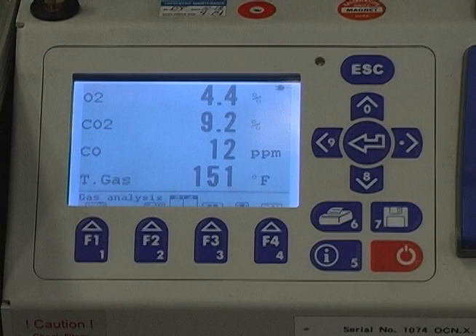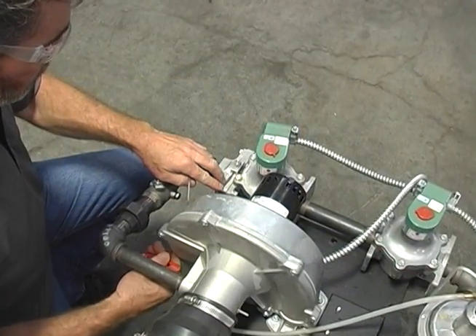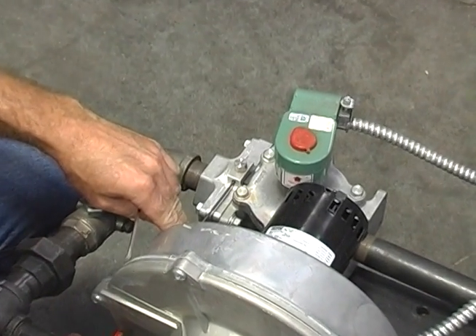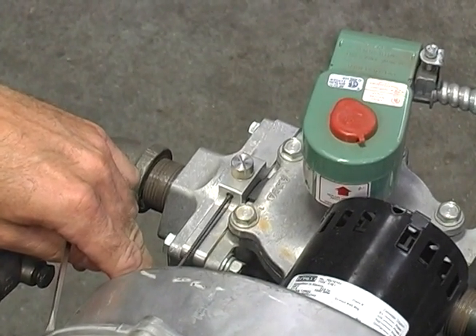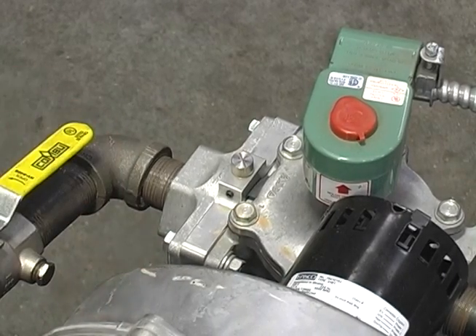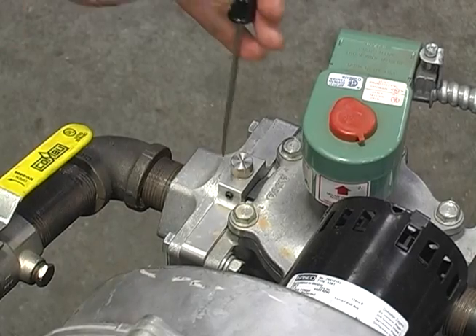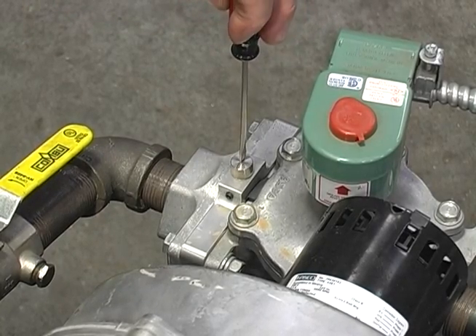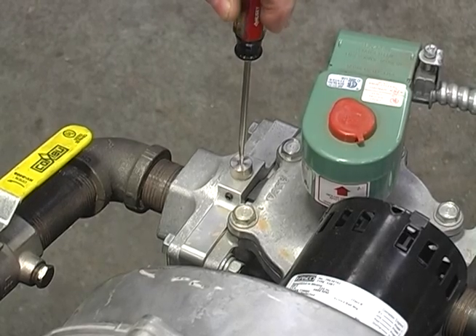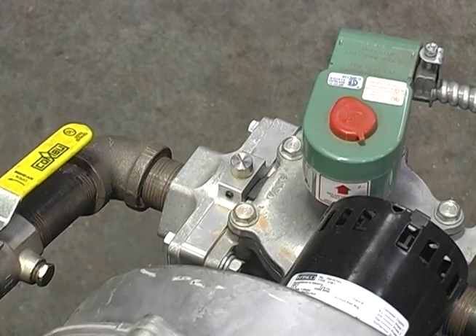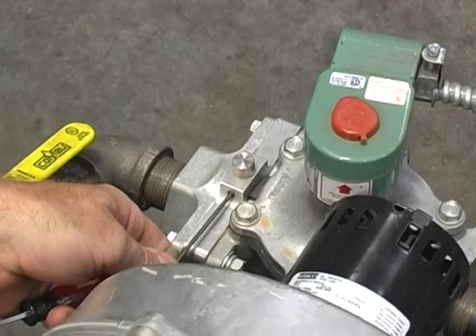At high fire, carbon dioxide level must be between 8.5% and 9.5% for natural gas and between 9.5% and 10.5% for LP gas. If the level is in this range, no adjustment is required or recommended. If the CO2 level must be adjusted, the high fire CO2 adjustment is made on the gas valve. First, loosen the set screw on the side of the valve body. Adjust the valve orifice clockwise to reduce gas flow and counterclockwise to increase gas flow. When CO2 is in the proper range, tighten the set screw to lock the gas valve adjustment.